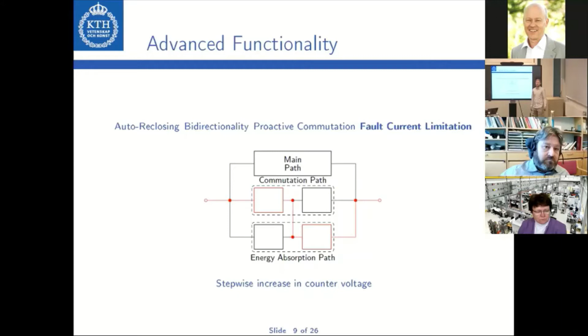Let's have a look at the state where the commutation path already conducts. It is now possible to operate these modules independently of each other. If, for instance, the second module in the commutation path is turned off, the current will commutate to the parallel connected module in the energy absorption path. Now only one module in the energy absorption path is inserted, and this means that the inserted counter voltage is also reduced. If even more modules are added, for instance 4, 8 or whatever, it is possible to stepwise increase the counter voltage and to limit the fault current or even control it.